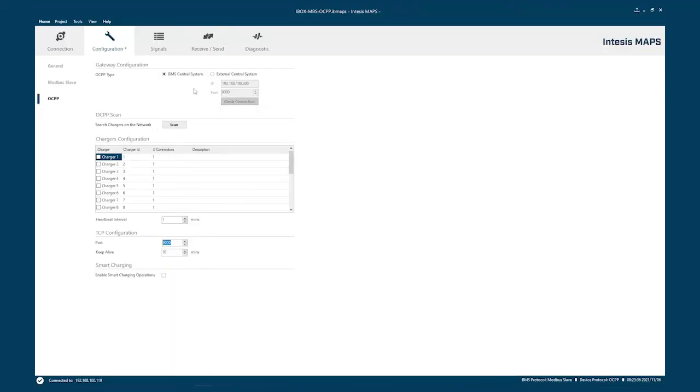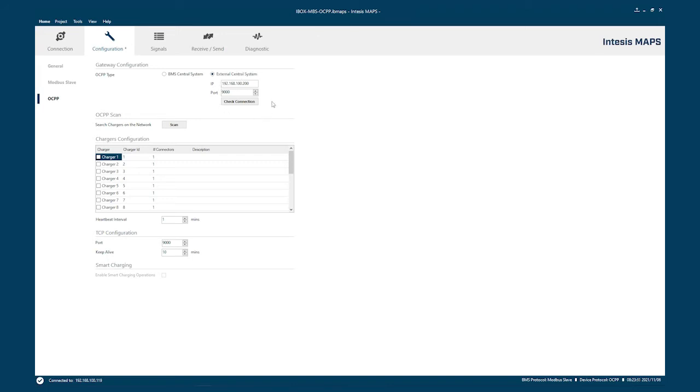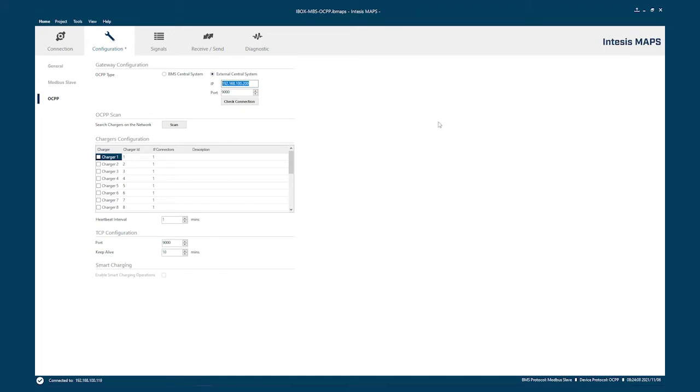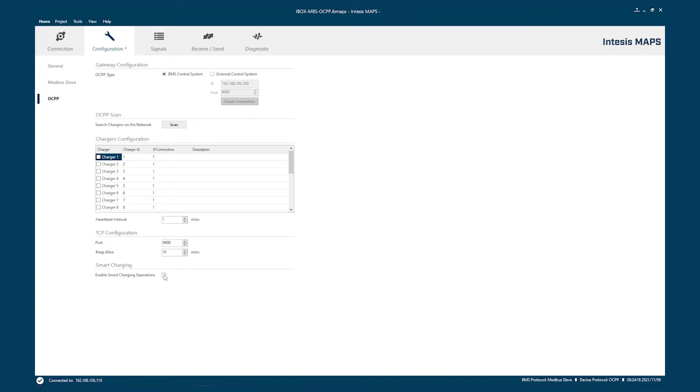So we will choose to be a BMS central system. Here is where we have to authorize every transaction. If we have an external system, we will go through this option. Please notice one thing here. We'll have to put the central system parameters and the port of that external system. When you have that selected, you don't have option to select the smart charging because this will be done by the external central system. We'll keep it in BMS central system. We will leave this enabled for later on as we will go through this new feature, smart charging operations.